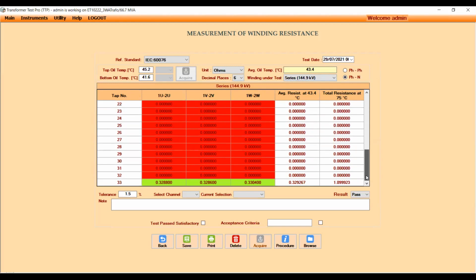You will wonder how the report is going to appear when it gets printed. Yes, this red colored data, that 00, means the test has not been conducted on those taps; they will be skipped, and the report will show the normal tap and the extreme taps only. So this is the way the whole thing is going to happen as far as the winding resistance test.